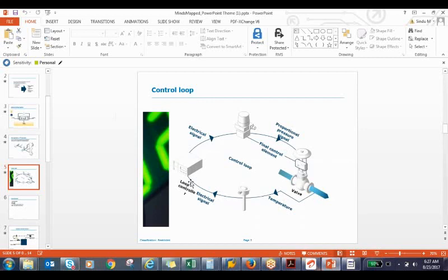So you have measured the temperature and you felt that the temperature is more by a particular value. The purpose of the PLC or controller is to say by what percentage or what level the temperature is higher or lower. That difference we convert to a proportional pressure signal. So this is basically an I2P converter. From the loop controller, you will have an I2P converter that converts the difference in the signals, or the requirement, to a proportional pressure signal, and that pressure signal goes to the valve for opening or closing.